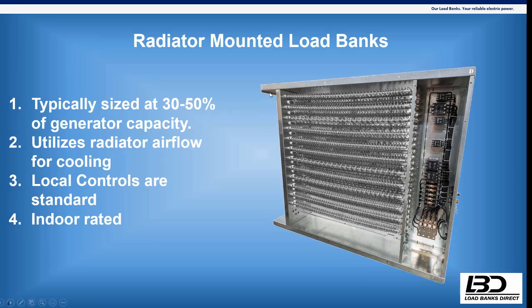With a radiator mounted unit, we could have a unit where this window is 8 foot by 8 foot wide and only have 200 kW in it. But we could also have one that is 8 foot by 8 foot wide and has 400 or 500 kW in it, or even smaller. It just ranges depending on the radiator, the amount of airflow required, and the capacity of the unit. So each one is a custom drawing, or a custom unit, depending on the face of the radiator and options selected, such as remote controls versus local, and other options.